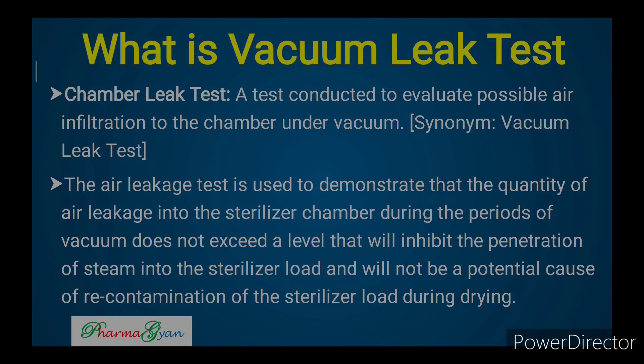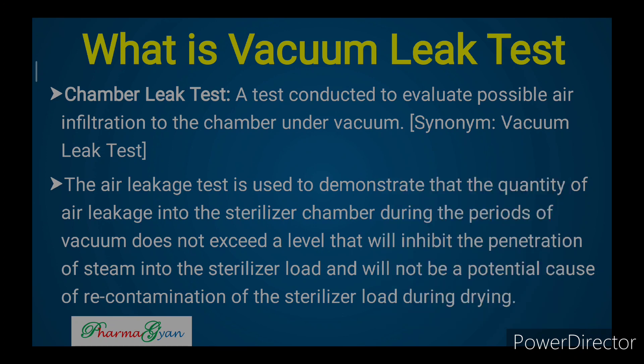So what is vacuum leak test? Vacuum leak test, or chamber leak test, is a test conducted to evaluate possible air infiltration to the chamber under vacuum. The air leakage test is used to demonstrate that the quantity of air leakage into the sterilizer chamber during periods of vacuum does not exceed a level that will inhibit the penetration of steam into the sterilizer load, and will not be a potential cause of recontamination of the sterilizer load during drying.